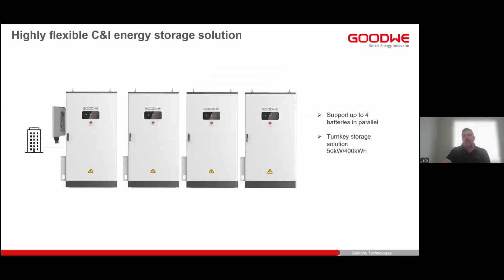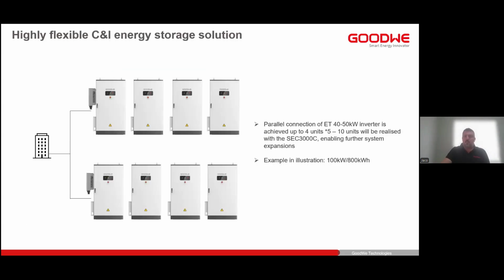The Lynx C battery, or the outdoor battery, supports up to 4 batteries in parallel, which means you can have a 50 kilowatt inverter with up to 400 kilowatt hours of dedicated storage. And then the entire system can also be paralleled to achieve multiple inverters, up to 4 with UPS level switching, and then, as mentioned, up to 10 for off-grid scenarios. So in this example, we have 100 kilowatt of inverter power with 800 kilowatt hours of battery power.